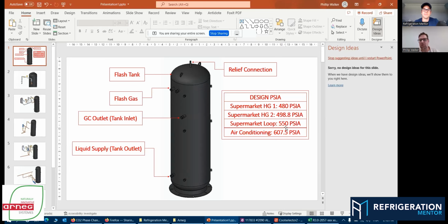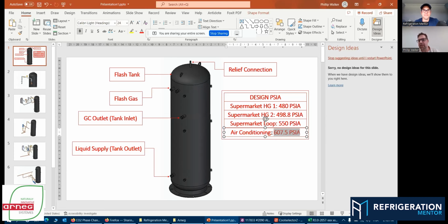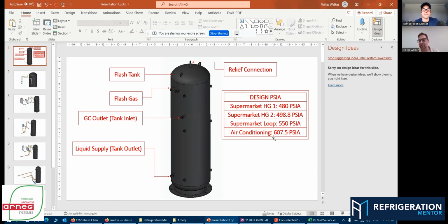The tank is running between 500 PSIA and 550. When we get into some air conditioning, we're about 607 to 610 PSIA. It's only because our suction temperatures are so much higher, right? So that's just a snapshot. I wouldn't say that's for every manufacturer out there, but if you're working on an Arneg system, this is basically where we're at and how we're designing our flash tanks, okay?